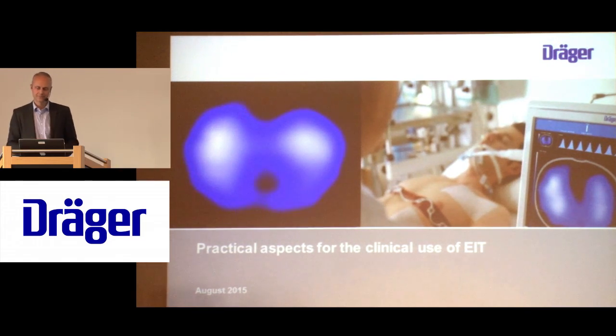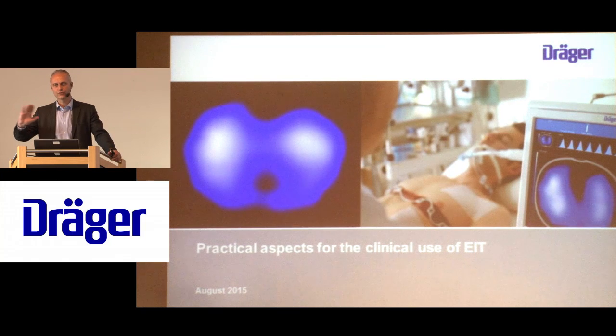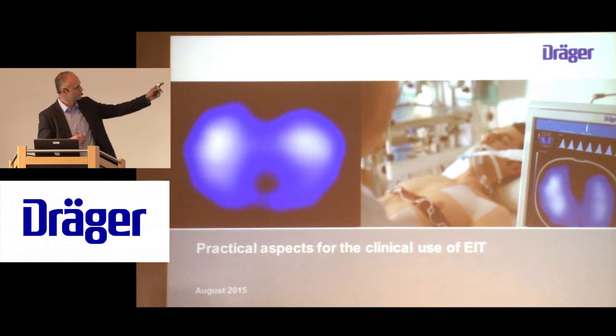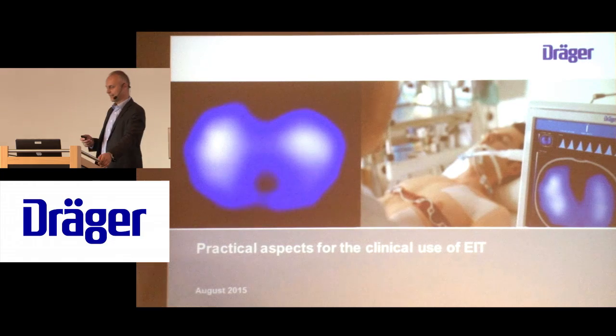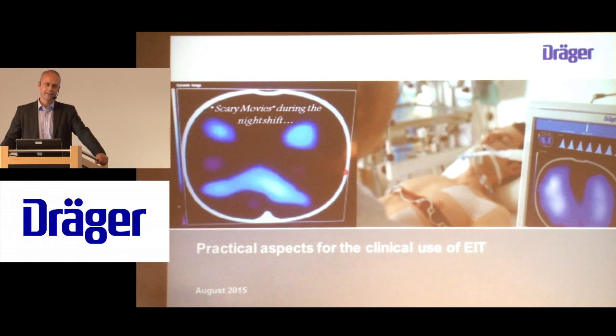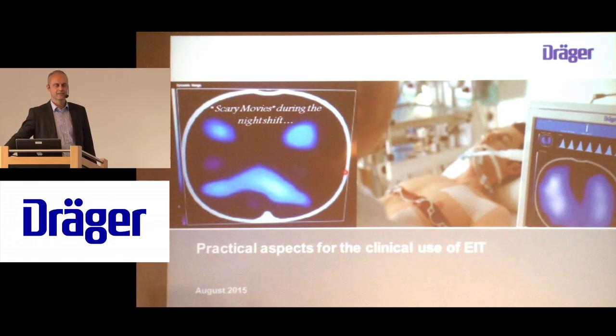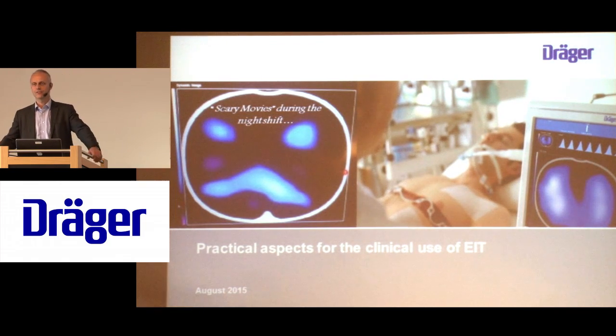But before we do that — when we introduced electrical impedance tomography as a medical product three years ago, I was so proud and relaxed because I knew we had solved all the technical issues. I was expecting that all users of the new technology would produce these kind of images. But I had to find out the hard way that sometimes the images looked slightly different. One morning I found in my email this image, and the doctor told me his night shift was scared about what was presented on the device. Because I received more and more of these images, I thought it's good to let people know what is actually causing these patterns, which has not very much to do with ventilation.